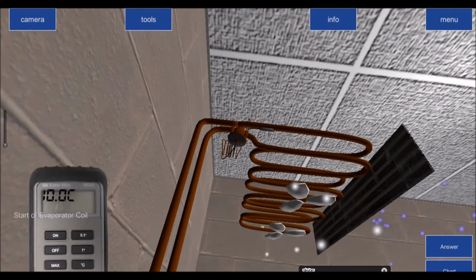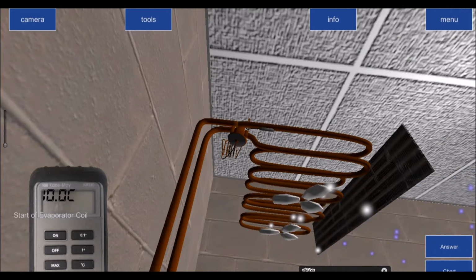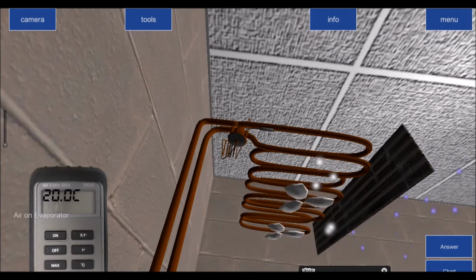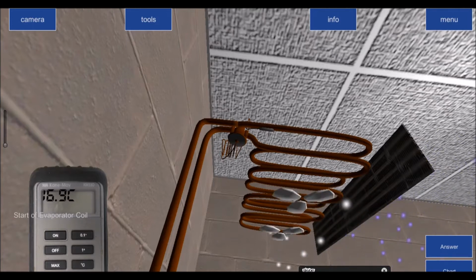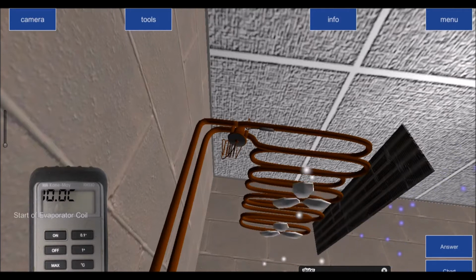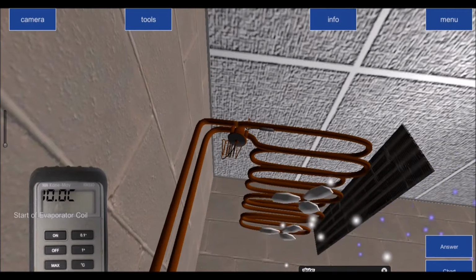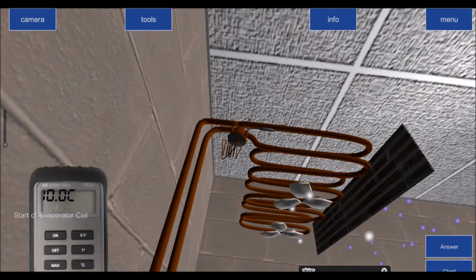Okay, that means that if the air on is 20 degrees, which in this case it is, we would expect the evaporating temperature to be 5 to 10 degrees lower. So if I take 10 off 20, that's 10 degrees, so that's within the range. But if I take air on at 20 and take 5 off, I can go to 15. So normal for an air on temperature of 20 degrees, normal evaporating temperature is anywhere between 10 and 15 degrees.